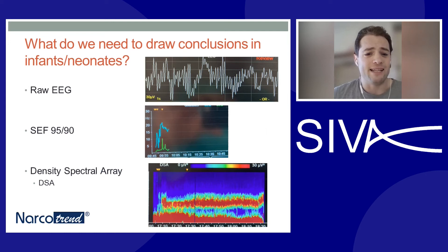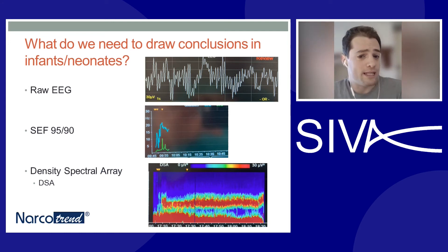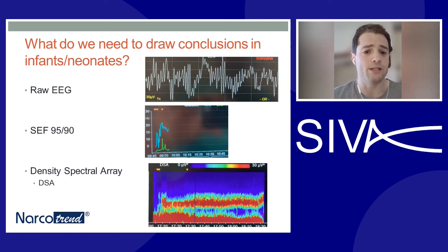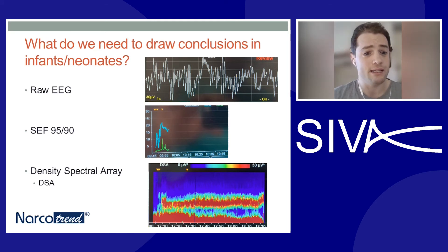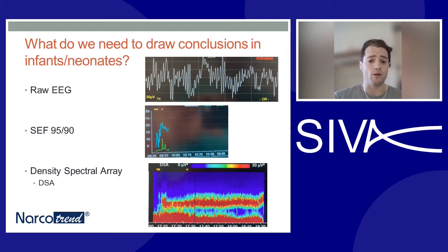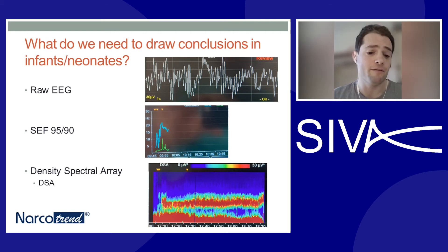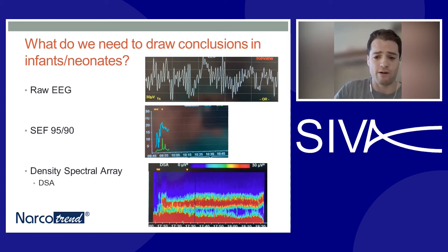Given that infants and neonates have these unusual changes, what do we need to draw meaningful conclusions in this cohort? We need access to three key things: first, the raw EEG; second, the spectral edge frequency 95 or 90, depending on which device you're using; and finally, the density spectral array, or DSA. All of those are represented on the right-hand side of the display.